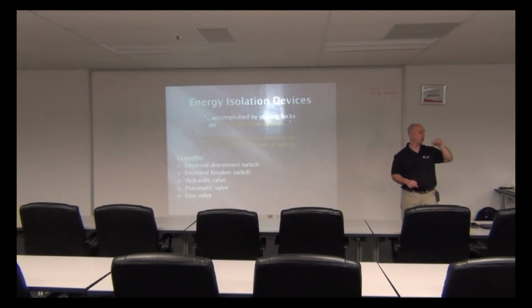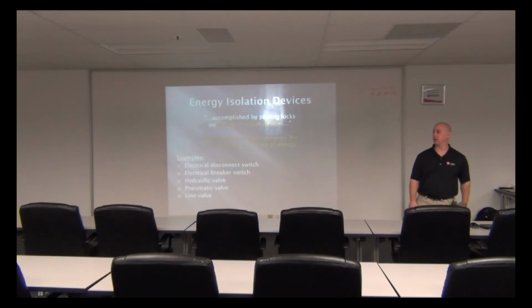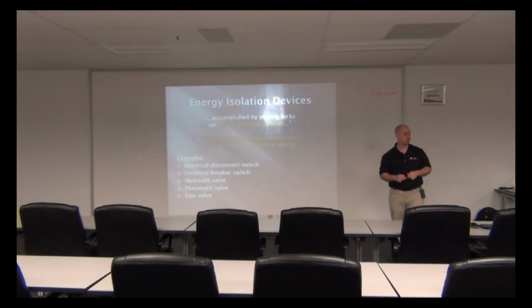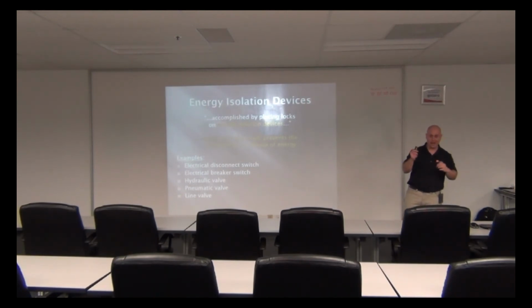So technically, when you do that, if you're not working on that box and you turn it off and the door can open, somebody can open that door and be exposed to a live electrical circuit. So there's actually two lockout points on that. There's the actual switch itself, and there's that little tab that pops out when you turn it off that you have to lock out as well. It's got a little lock hole on it. But I guess you could really just do the lock hole, but I'm not going to tell you that right now because I'd have to look at it more and say, would that actually work?